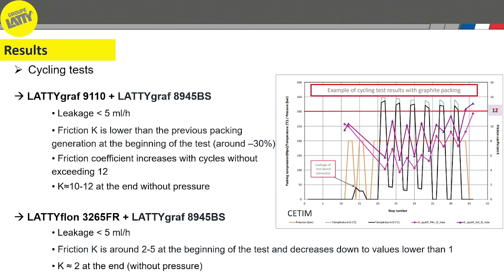For the PTFE solution, the same goes for the leakage: no leakage and no extra leakage was observed. In terms of friction coefficient, here we observed a very low friction coefficient, which tends to decrease as the cycling goes on until it goes down to a value of 1. After that, we did a test without pressure, and the results show that the friction coefficient was stable, averaging a value of 2. So this is for nominal operating condition.